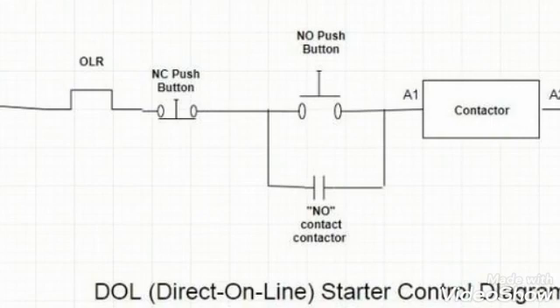Here in this diagram we will try to understand how the DOL starter works. Our phase from the MCB reaches to the overload relay, which is a normally closed contact, then to the normally closed push button which is our off push button, then to the normally open push button which is our on push button, and it reaches to the A1 terminal of the contactor. We have already given neutral to the A2 terminal, so the contactor will become energized.